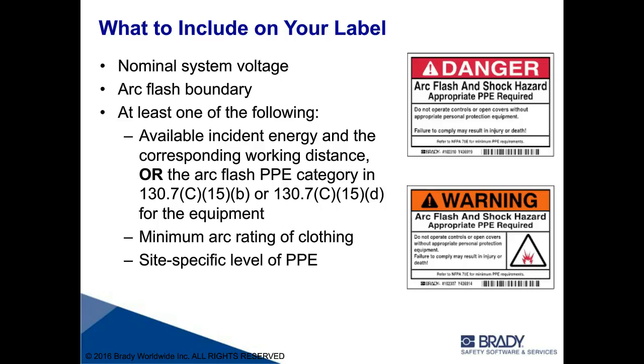That PPE category, or what used to be called the HRC category, is using the tables in NFPA 70E to look at: what's my situation, what's my equipment, what am I doing, and coming up with that 0, 1, 2, 3, or 4, which, as we talked about earlier, is now just 1, 2, 3, or 4. So when you look at labels, if you're having someone come out to do an energy analysis, you shouldn't have that 1, 2, 3, or 4 on the label. You should just match it up with whatever that incident energy is.